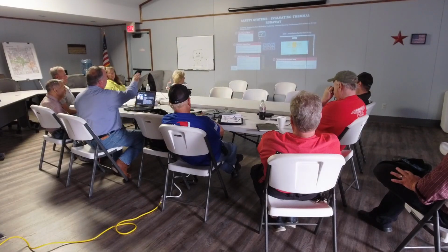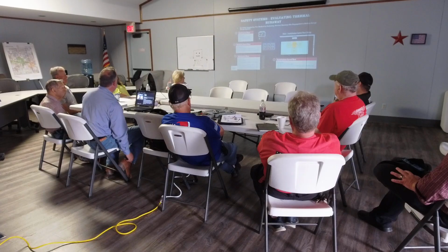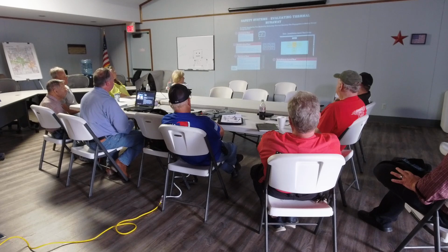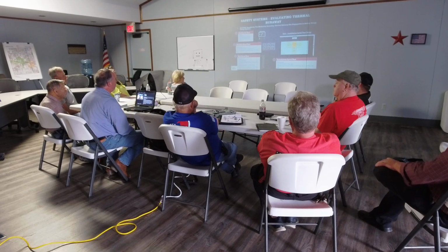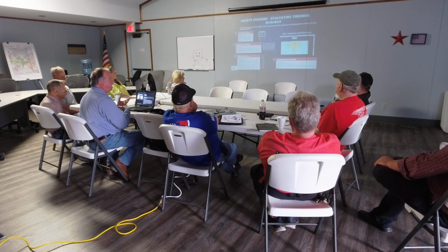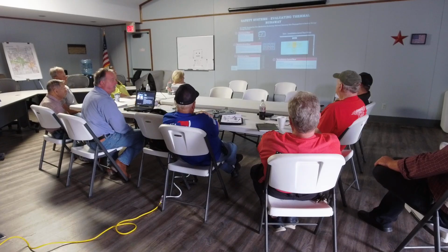There are 4 levels of testing that a battery has to go through to be considered for certification. It starts at the cell level. They'll initiate a thermal event, then collect and quantify all the gases and the heat, so we know how much each cell can produce.